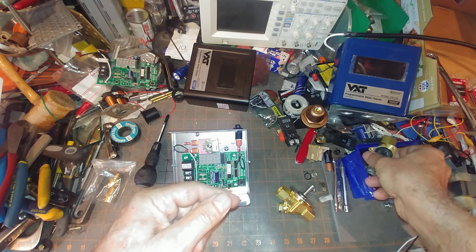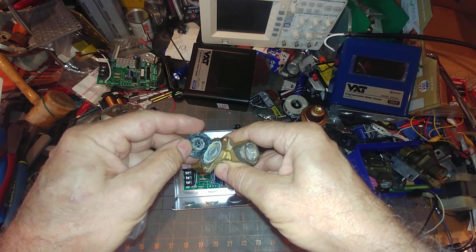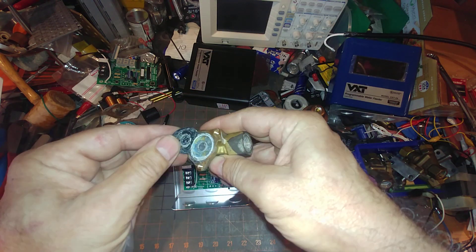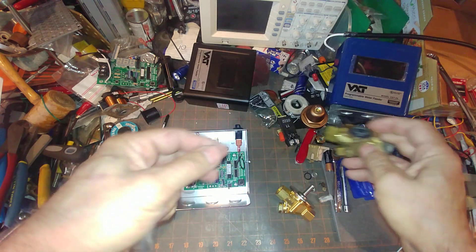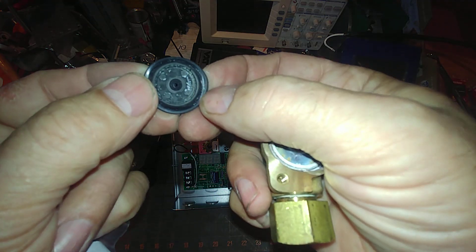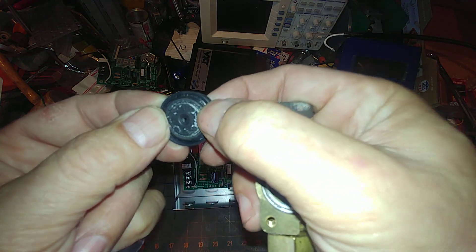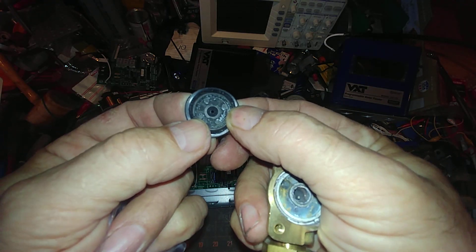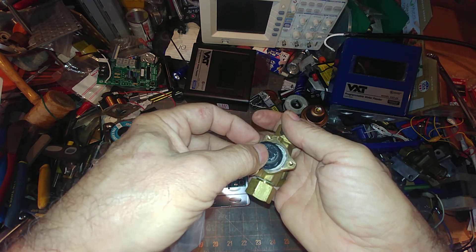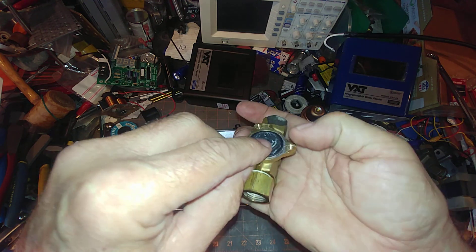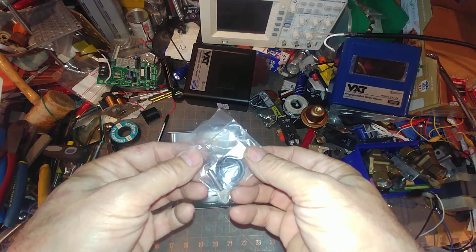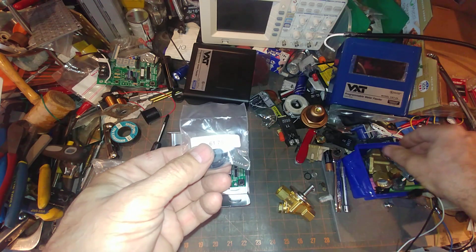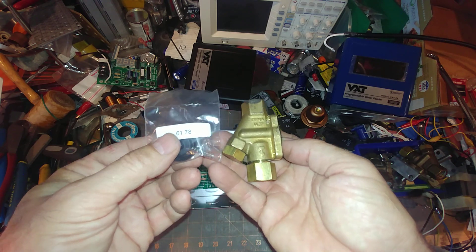Because it does calcify up over time. And so you can see, there's a little tiny hole right there. You've got two of them right there, and if both of them become clogged, then this thing will stick open and not cycle closed. So you want to be able to replace this, service this. The rubber does degrade.